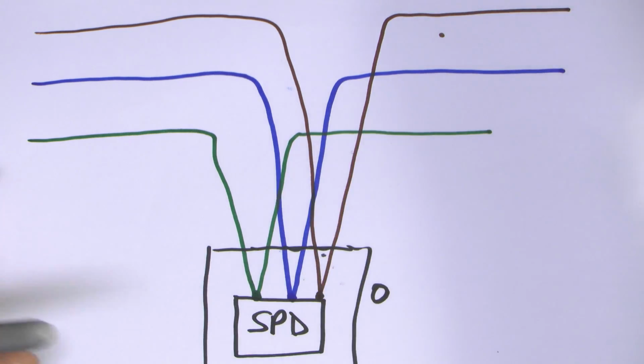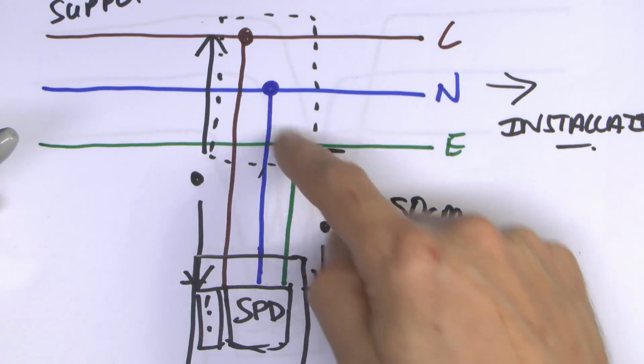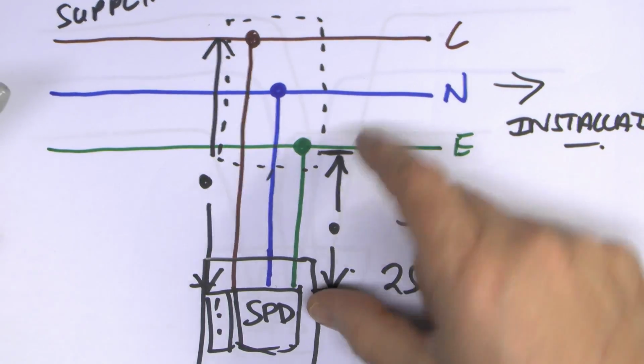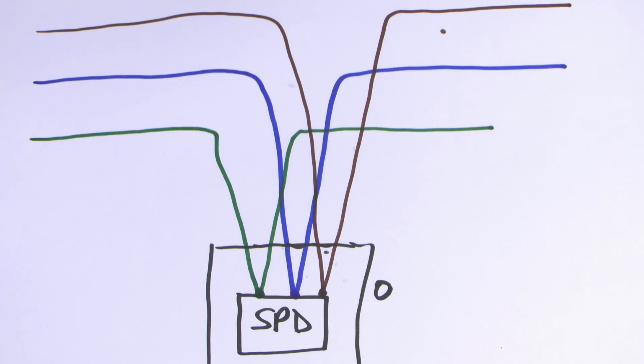So compare that with this one, where we had the wires going across and this was just tapped off on its own set of wiring. That's quite a large distance involved there. But in this case, because the wires actually come across to it, the distance is effectively 0, apart from this tiny little bit here where the terminals might be, so pretty much as short as it can possibly be. Now the disadvantage with this is that you're going to have quite large terminals on the surge protector device, but of course that's just a question of selecting the appropriate piece of equipment.